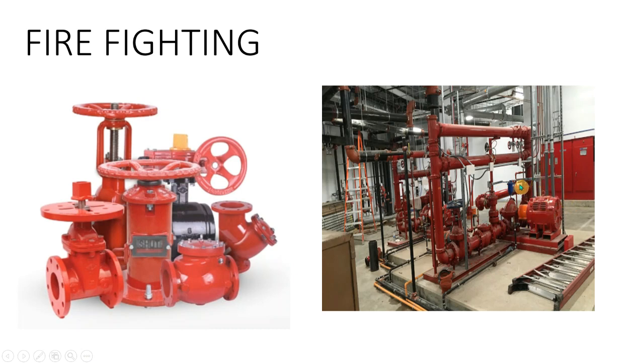With the help of the detailed drawing, you can find the connection details of each pump. For the electrical pump there will be some connection detail, for the jockey pump there will be some connection detail, and for the diesel pump there will be some other connection detail. When it comes to the diesel pump, there will be a diesel tank and also a measurement tool for the diesel level in the tank. Also there is a filtering system in case the diesel engine is in on position. When the diesel pump is on, the smoke coming out of it shall be exhausted, right? So in those scenarios, the filtering or exhaust system will be placed in your pump room.